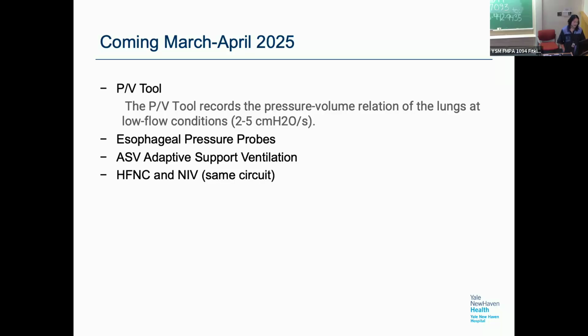So this ventilator has a PV tool, which they call the protective ventilation tool or pressure volume tool. And this records the pressure volume relationship of the lungs at low flow states. When used in conjunction with esophageal pressure probes, it will help us maybe target ideally the PEEP that we would want to use on the patient and have a better understanding of transpulmonary pressure.